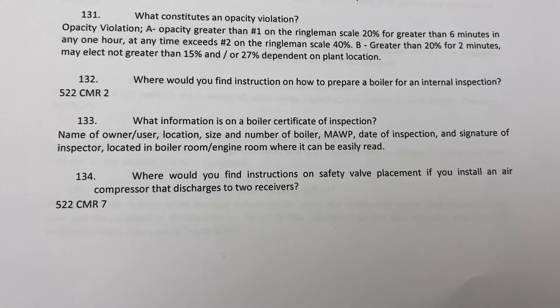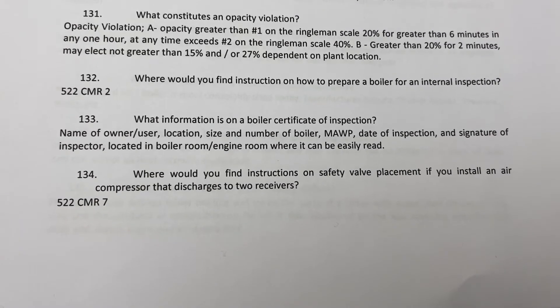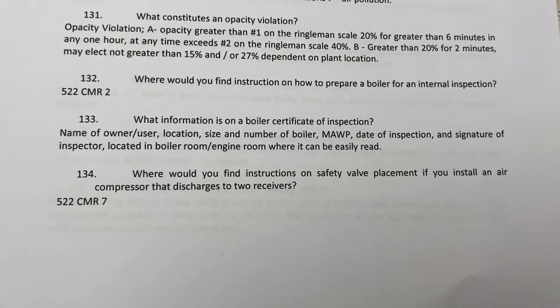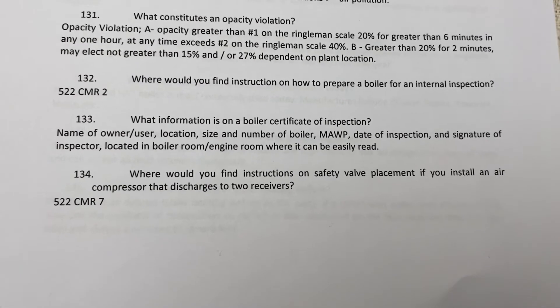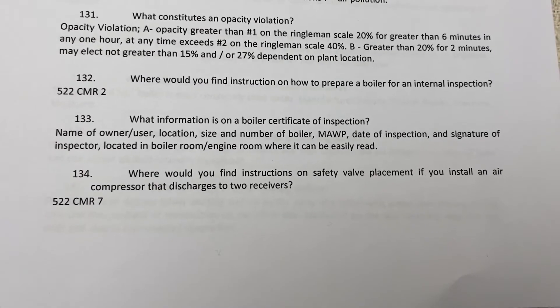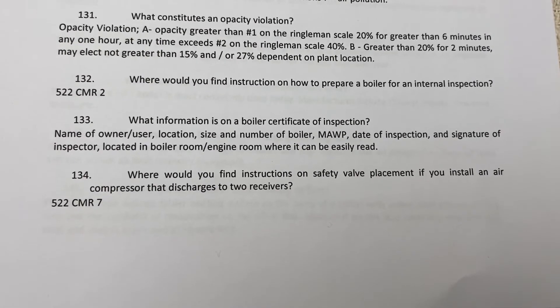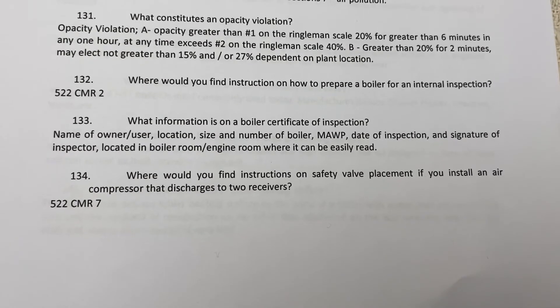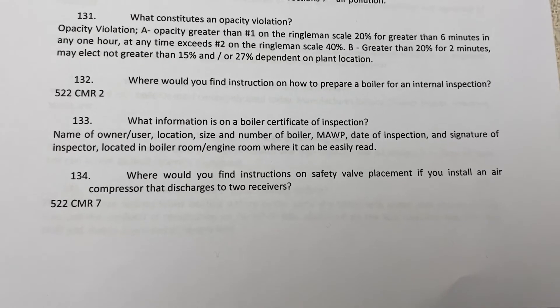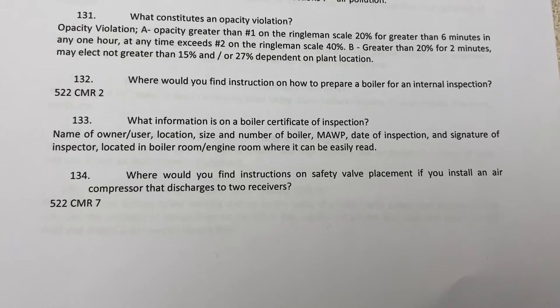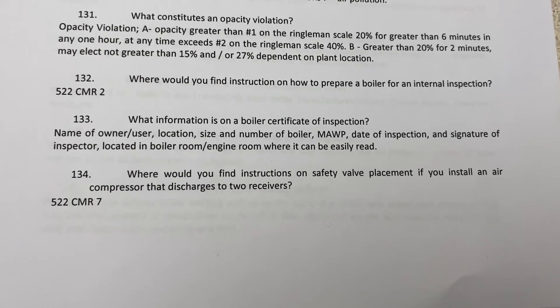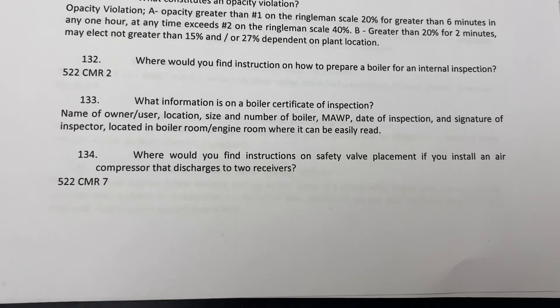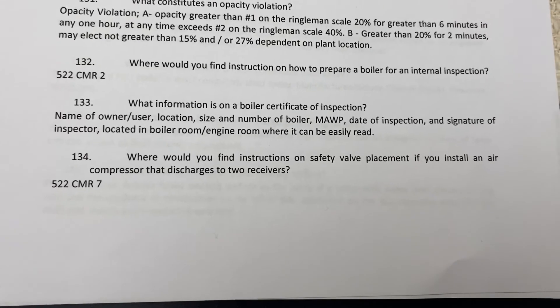What information is on a boiler certificate of inspection? The certificate includes the name of owner and user, location, size and number of boiler, maximum allowable working pressure, date of inspection, and signature of inspector. It must be located in the boiler room or engine room where it can be easily read.